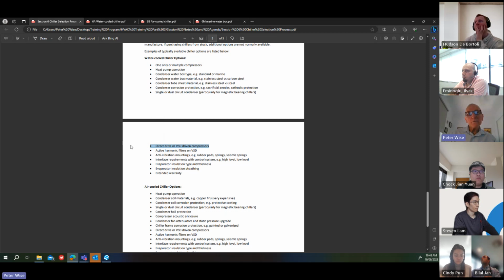You can get direct drive or VSD driven compressors. Magnetic bearing compressors are all VSD driven. They've got an integral VSD. But with other ones, screws and the larger centrifugal compressors, you can get VSDs as an option to improve the efficiency. You may want to put active harmonic filters on the VSD because that can cause problems with the electricity supply. VSD's frequencies can cause some issues.